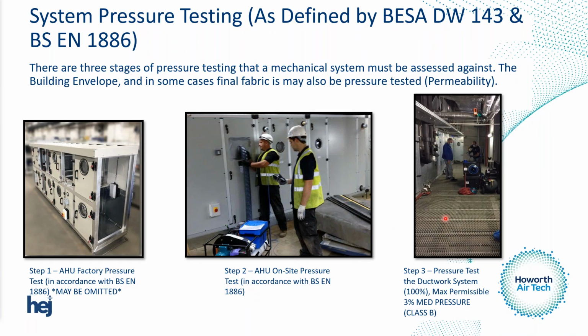Once that's adequate, obviously we connect the ductwork up, keeping DW143 and DW144 in our minds. We install the ductwork in accordance with that. And then the ductwork must undergo a pressure test. 100% of the ductwork must be pressure tested. We don't want to be taking sections of ductwork or leaving existing ductwork half tested and not tested. The full system has got to be tested. If we're starting from scratch, we've got to start at this point. And the classification of that ductwork is Class B.